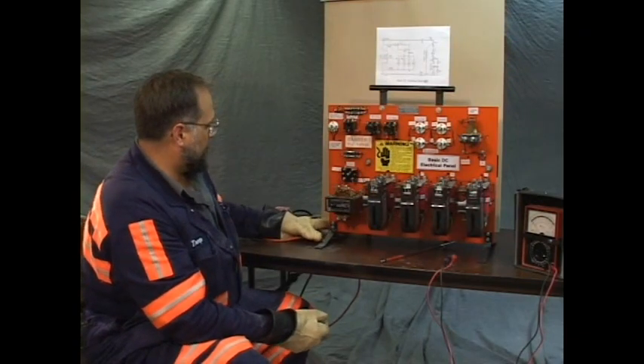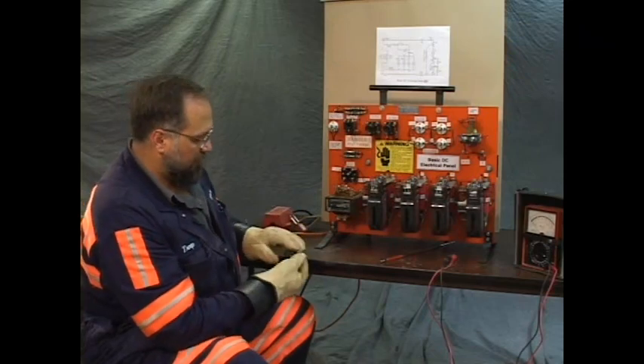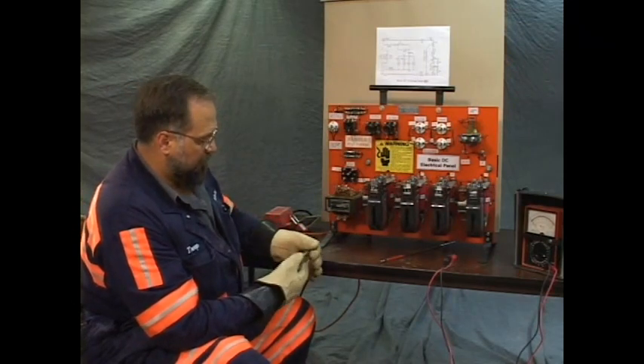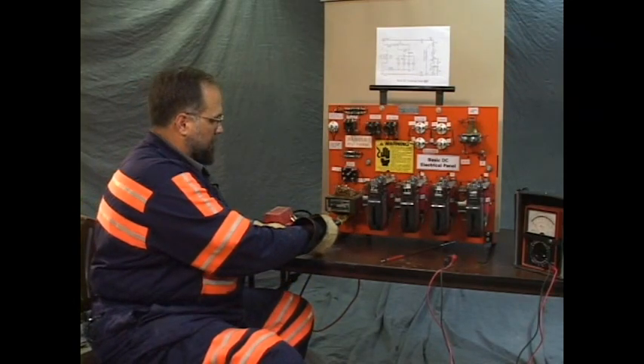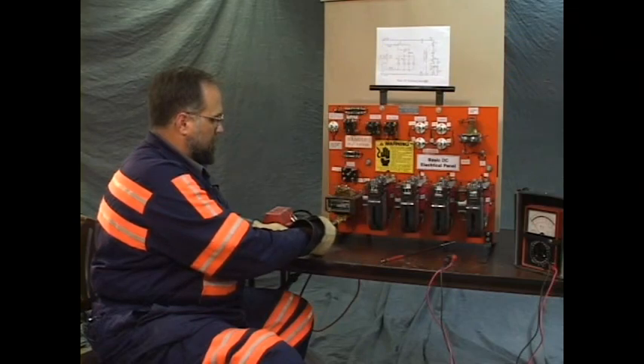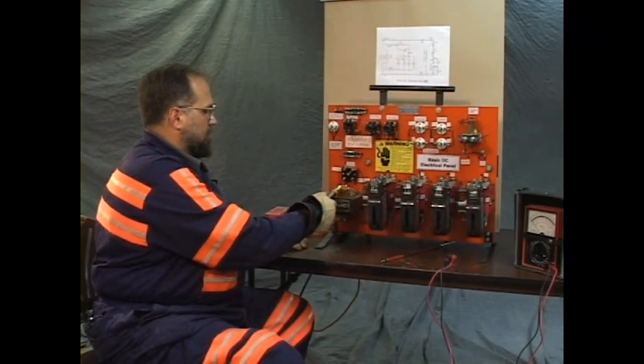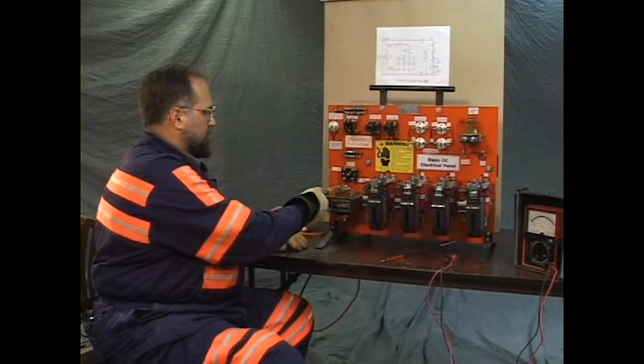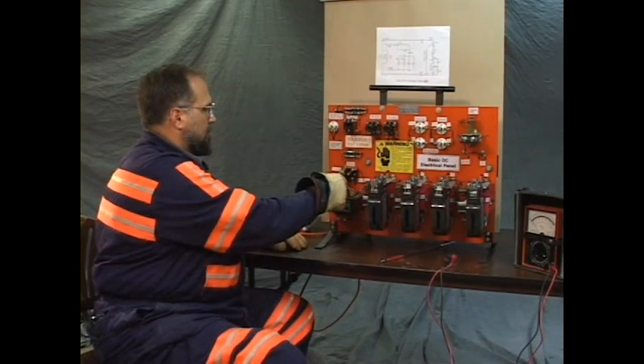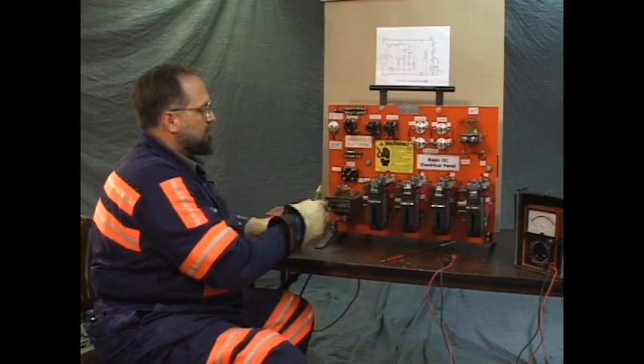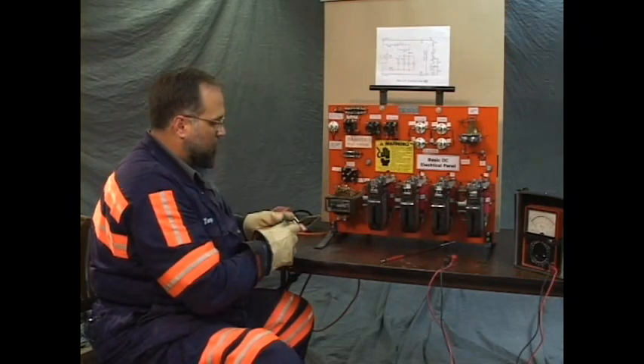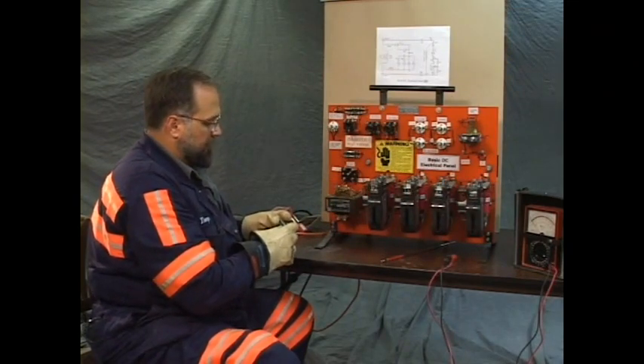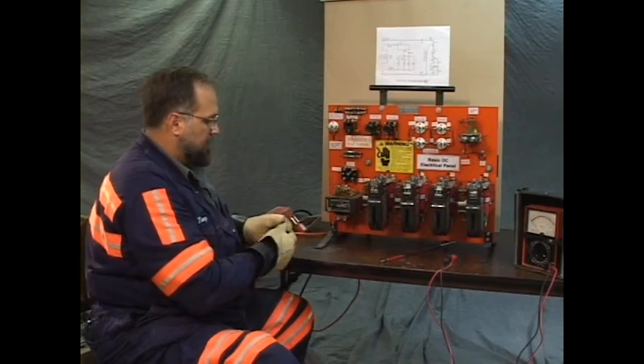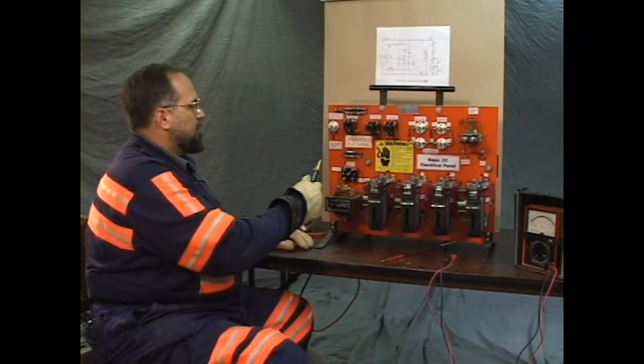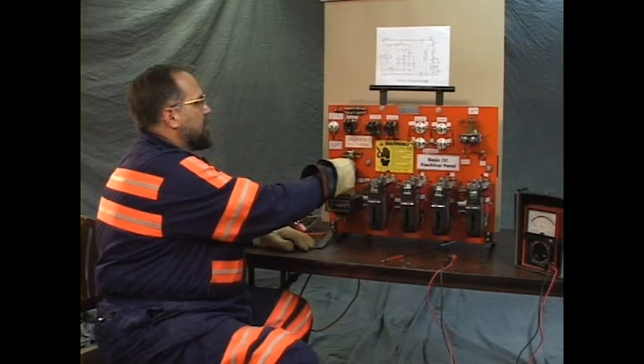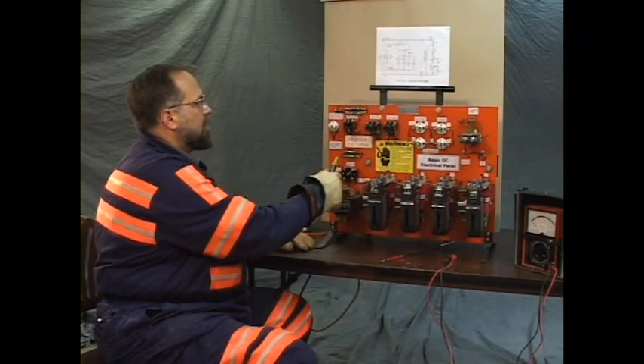Okay, we've taken the power off. I'm going to take this voltage detector. These voltage detectors are very sensitive. They've got a wide range from 50 volts to 1,000 volts AC as it's listing. I believe it'll pick up a somewhat smaller voltage than that, and it does respond to sudden movements.